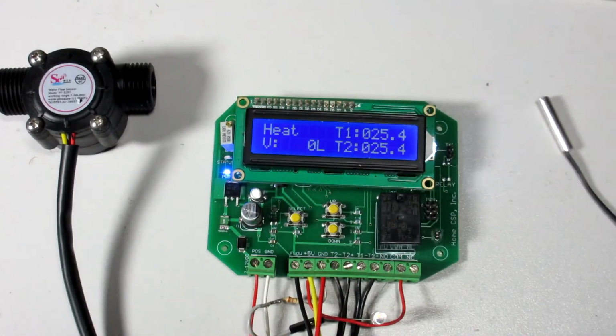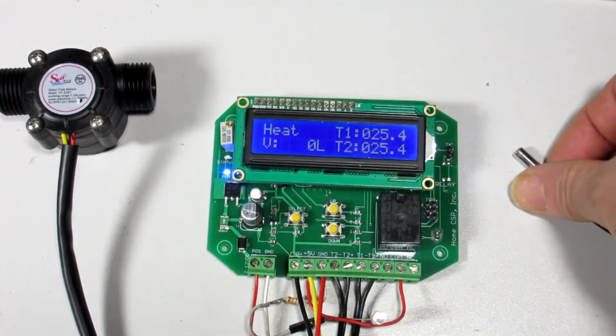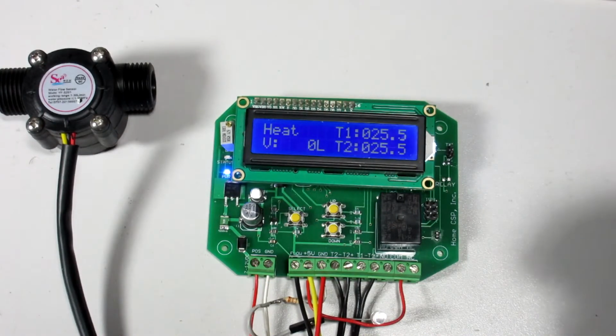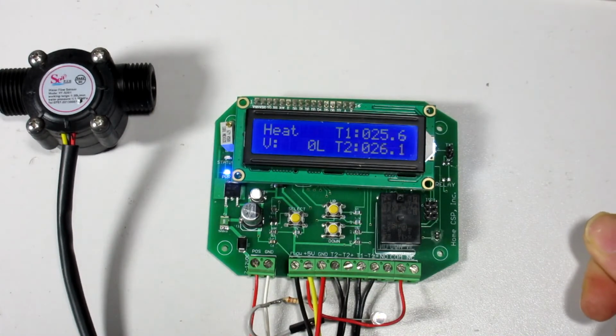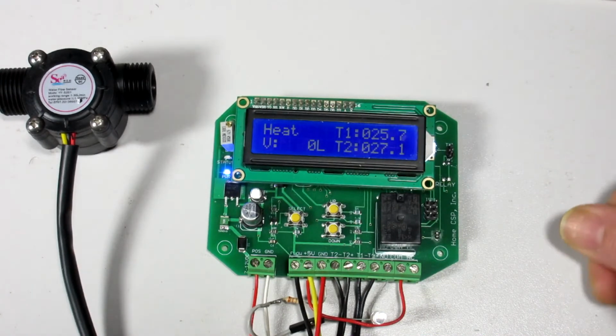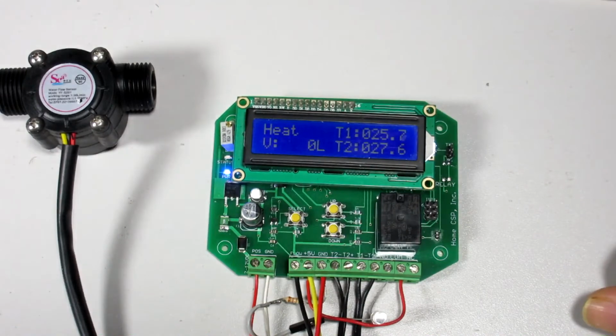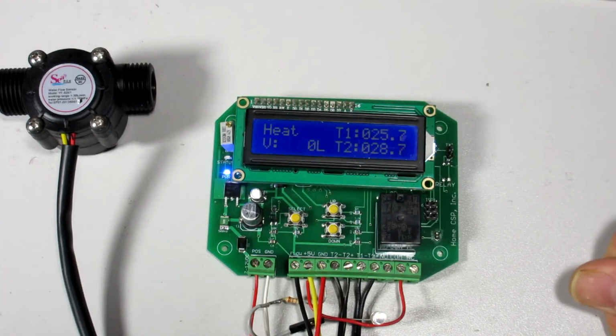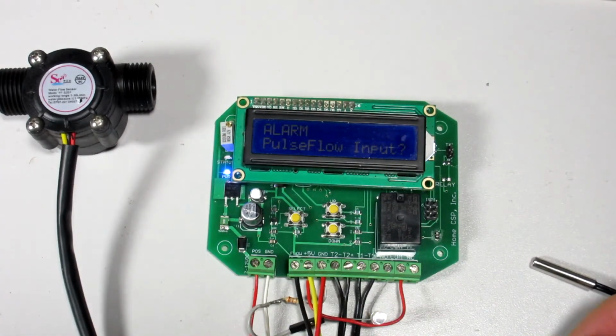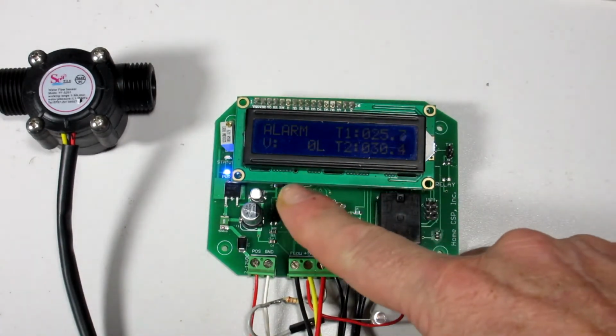So I'm going to take the T2, hold it in my hand. I'm going to see it go up a little faster than the other one here. Okay, so when that hits 30 or so, 30, because that's our min, trigger the relay. There we go. So it went high and then low, and then it said alarm.